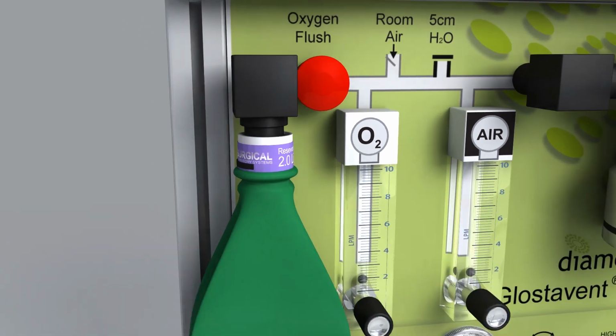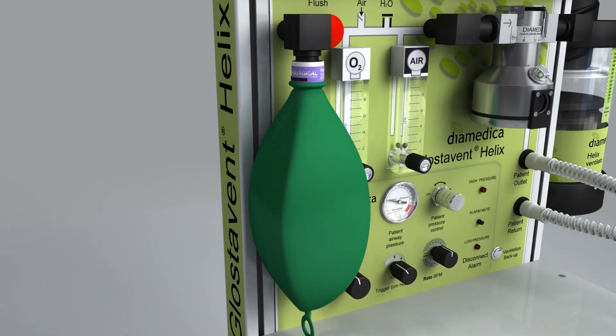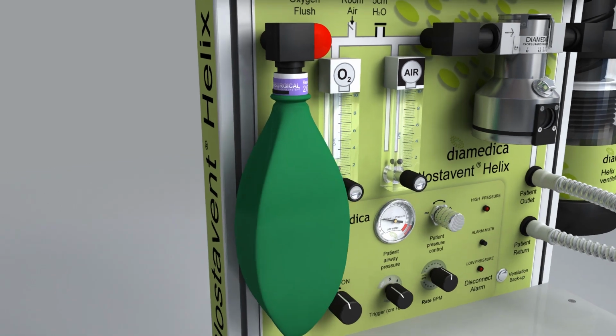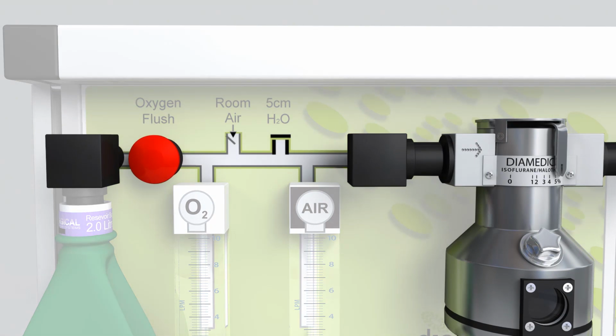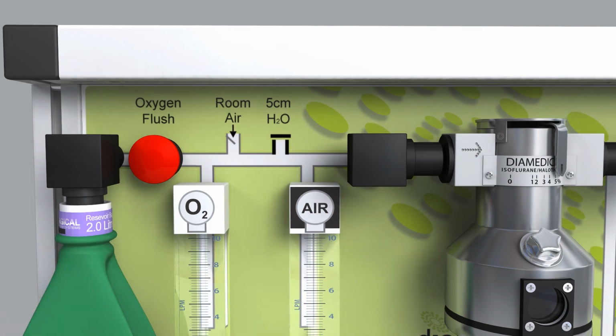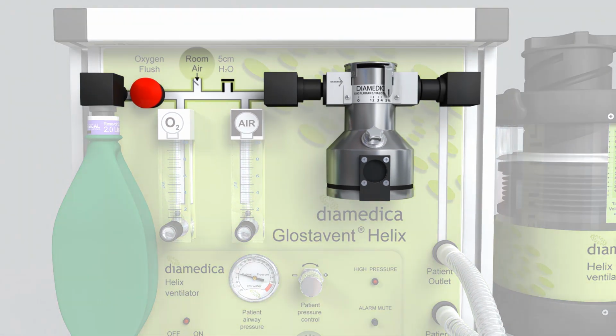The reservoir bag is fitted to the back bar and stores the oxygen and air mixture up to a maximum of 2 liters. Once the reservoir bag is full, there is an overpressurizing valve fitted to the back bar, which relieves at 5 centimeters of water pressure. The overpressurizing valve protects the patient by preventing the circuit from overpressurizing. There is also a one-way valve connected to the back bar to allow room air to be drawn in if the patient's minute volume is greater than the gas mixture being delivered. In an emergency situation, the system can be flushed with oxygen using the oxygen flush button.